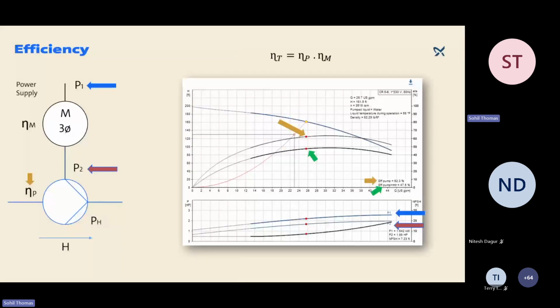Now, a little information on what efficiency looks like and what parameters we have as far as a pump is concerned. From the slide, you can understand that the overall efficiency is a combination of both the motor and the pump efficiency. So all the electrical input provided to the motor is not converted into hydraulic power. As you can see over here, the efficiency of the pump alone was close to around 62.3, whereas when you club the motor along with the pump, it dropped down to 47.5. So we need to make sure pumps are working at the best efficiency point to make sure that energy is consumed at the lowest level. You can see the efficiency curve here, which I want you to remember, how this curve went up and dropped down as it goes towards the far right end of the curve.